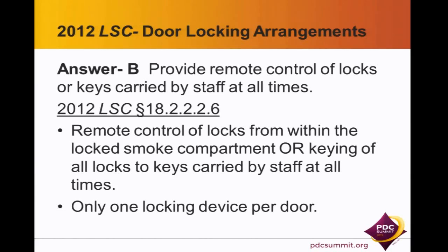And so you need remote control of locks from within the locked smoke compartment. That's very important. Or you need keying of all locks to be carried by staff members at all times. And there is a limit to only one locking device per door. So you can't have a multiple setup even if there's a security issue.